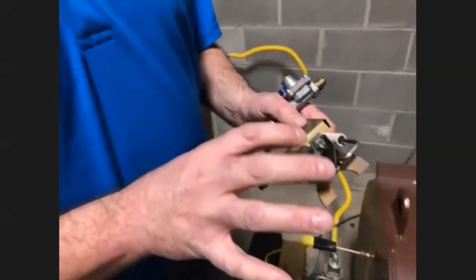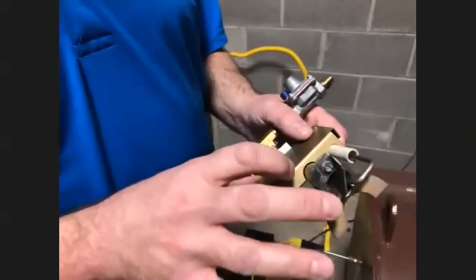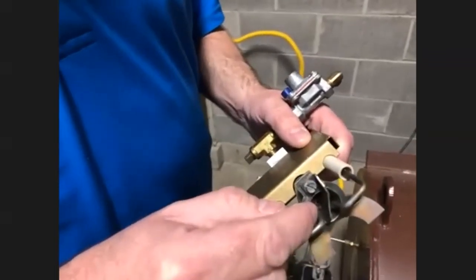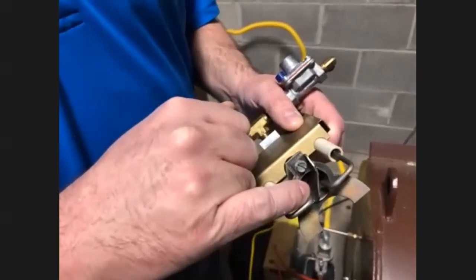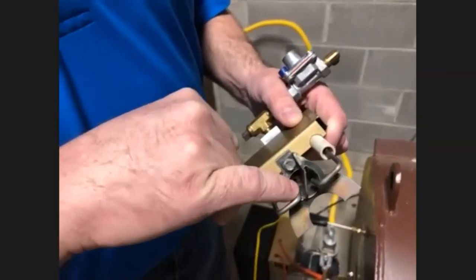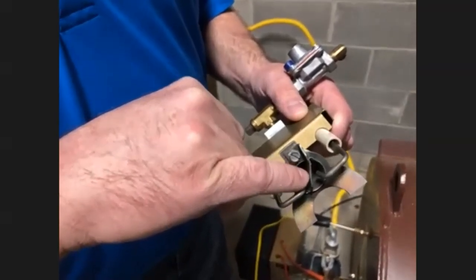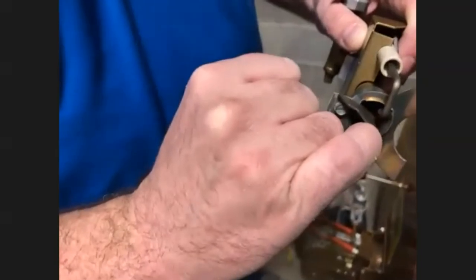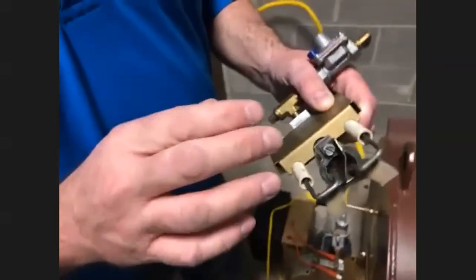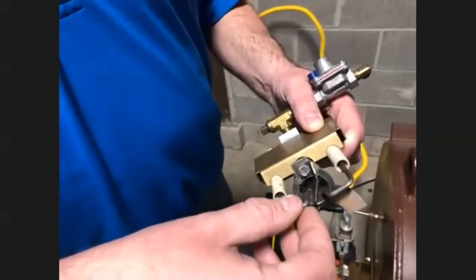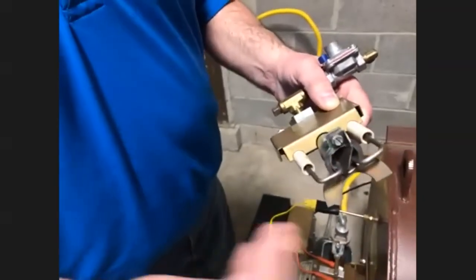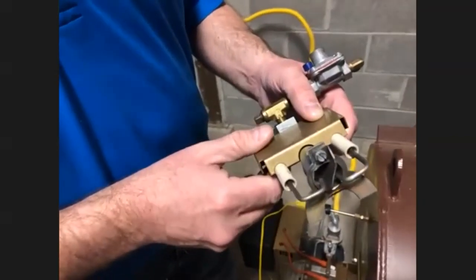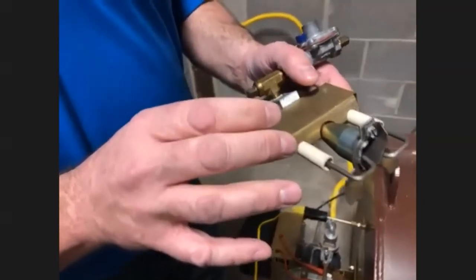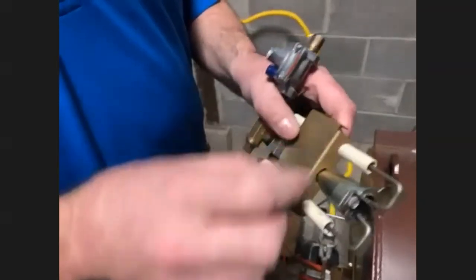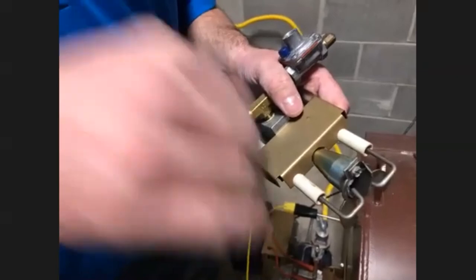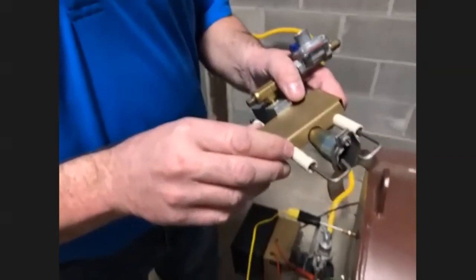Another thing to verify when you have spark issues is to make sure your spark gap is set properly. You need to have 1/8 inch to 5/32 inch between this igniter and this ground plate. Remember, 1/8 inch to 5/32 inch. If those are rotated out of place and you have too much of a gap, the spark will not jump across and it will not create your ignition. You also want to look for cracks in the igniters themselves. If there are cracks in these housings, moisture can get in and prevent them from operating properly as well.